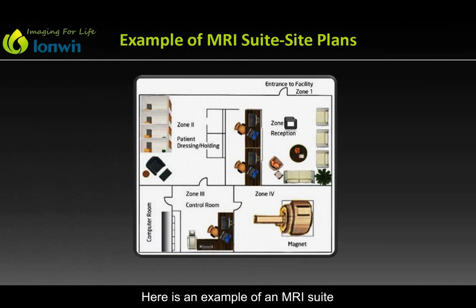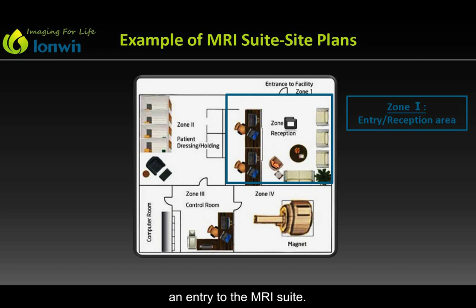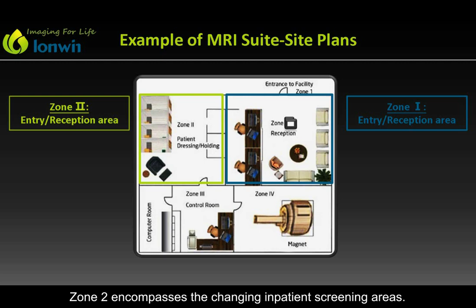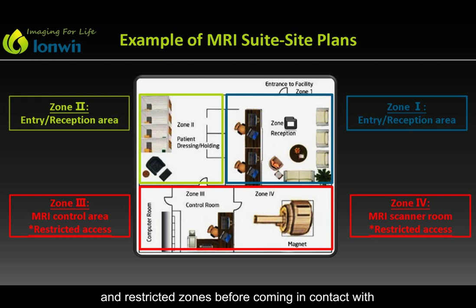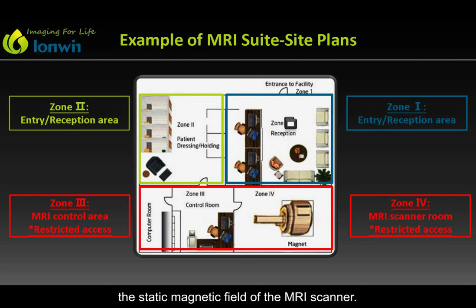Here is an example of an MRI suite where Zone 1 is the reception area, an entry into the MRI suite. Zone 2 encompasses the changing and patient screening areas. Zone 3 contains the MRI control area and entry into Zone 4. Zone 4 is the MRI scan room itself. This departmental design reduces the chances of individuals accidentally entering the MRI scanner room because a person must pass through the supervised and restricted zones before coming in contact with the static magnetic field of the MRI scanner.